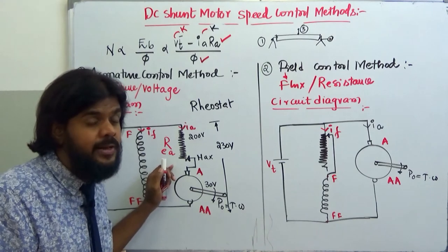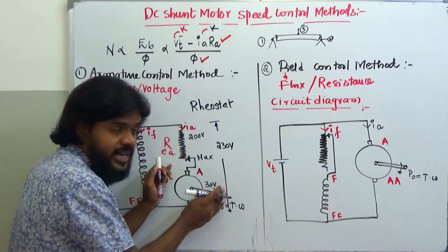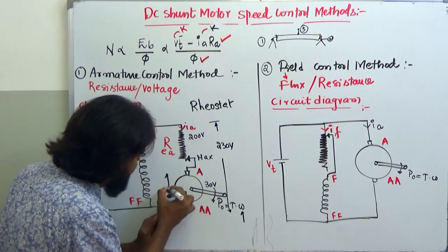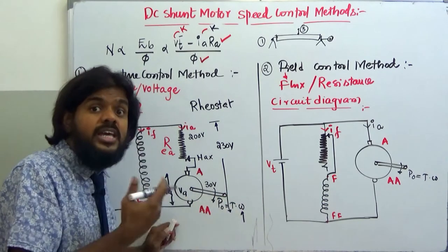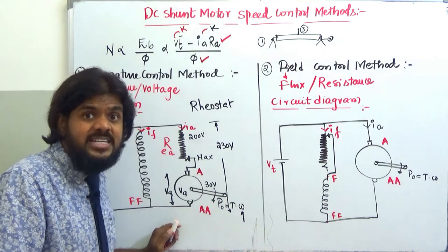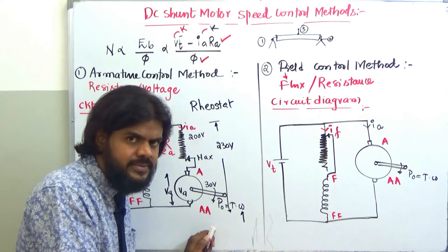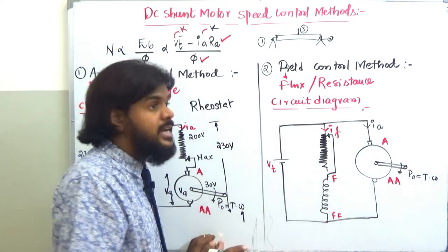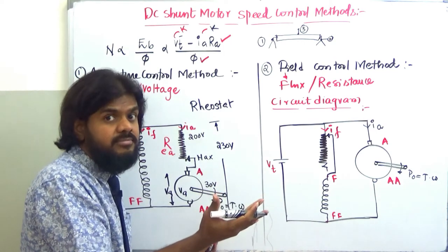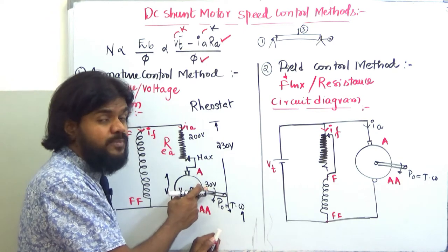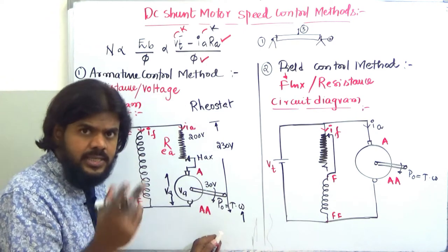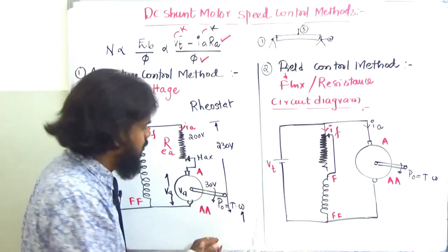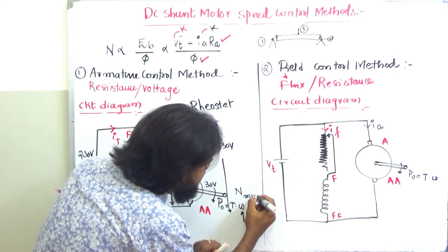So the armature voltage Va is very low. If you kept a very high resistance value there, the voltage drop across it could be 230 V and the voltage at the armature would be zero — meaning the output speed would be zero. So the motor starts at a very minimum speed in this configuration.